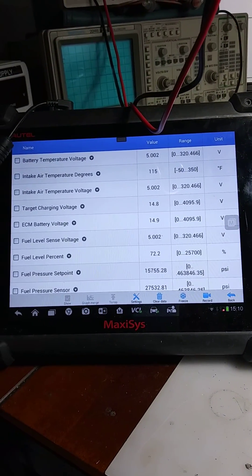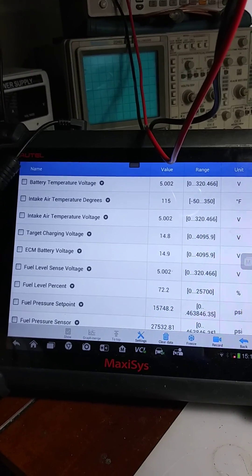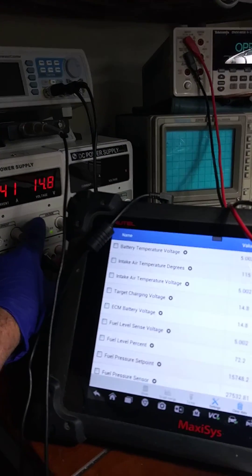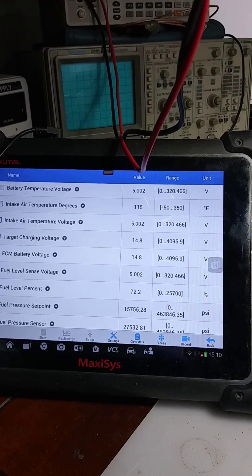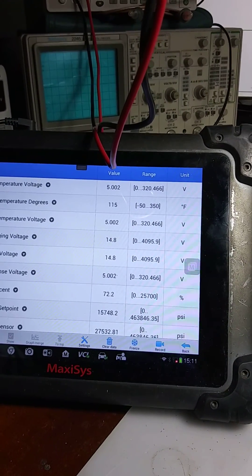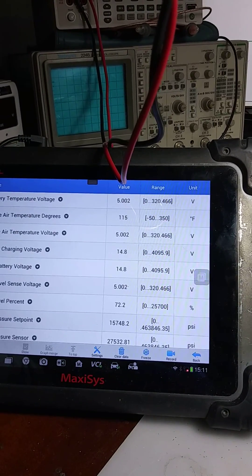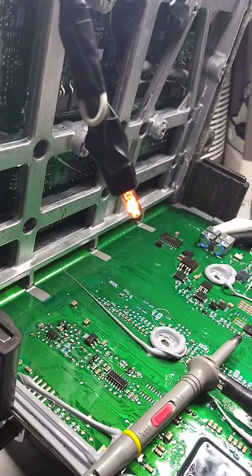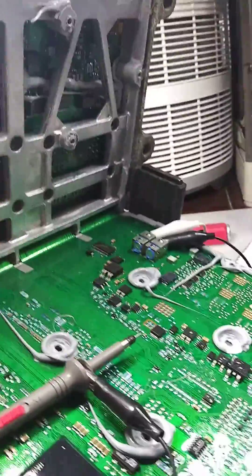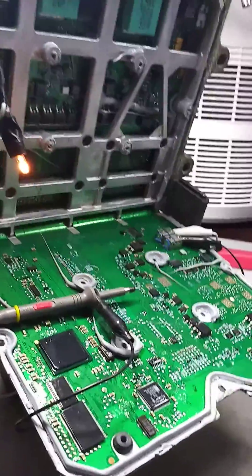At 14.9 we have it off. Let's see if I can get 14.8 — that's 14.8, we have it off, so that's a perfect target. Let's try 14.7 — and we see it back on. So, working as it should in the engine controller here.